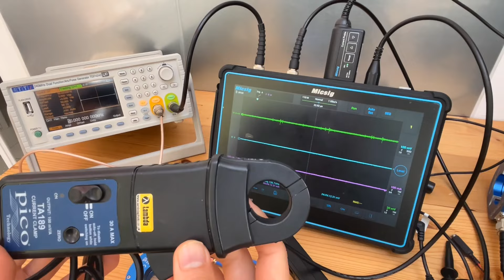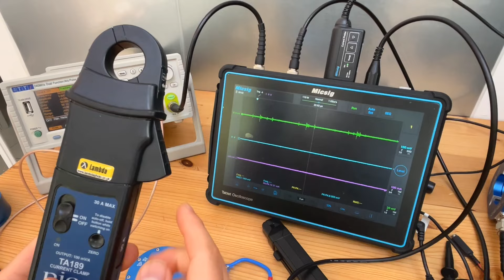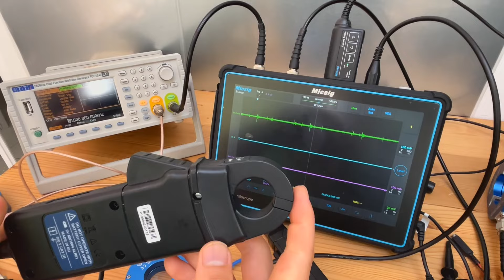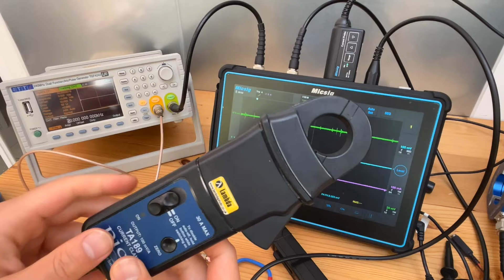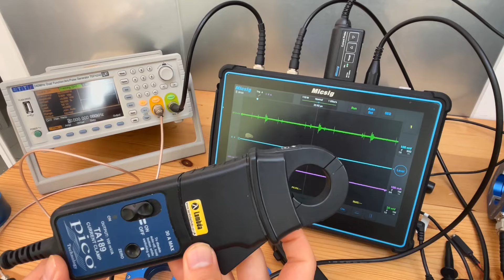This is a 30 amp rated Hall effect based current probe, and it can measure current up to 30 amps maximum. I use this a lot for harmonics analysis and things like that. But I just wanted to demonstrate that probes such as this are designed for low frequency measurement, so they don't actually focus on E-field shielding.